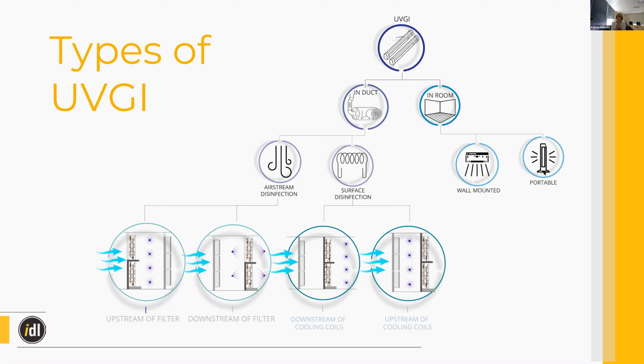So the key with UV, in room and in duct, but particularly in duct, is that it's installed right. If you're going to try and disinfect the airstream, you have to make sure that you have a high irradiance and that air is coming into contact with the UV light for long enough to disinfect. And same with surface disinfection, sometimes you deal with changes in humidity and temperature within that air handling unit, and that can affect the efficiency of those UV lamps. So great in theory and a lot of times in practice, but it does take a lot of monitoring and controls to install it right and maintain it right.